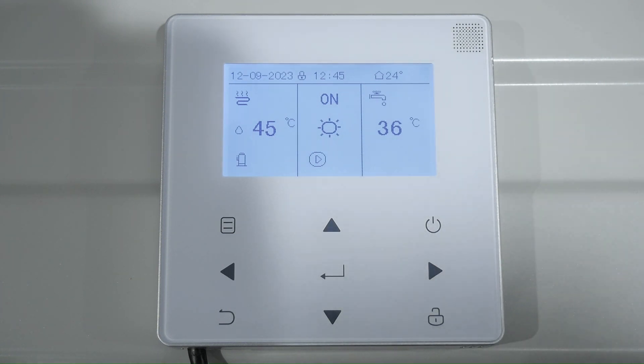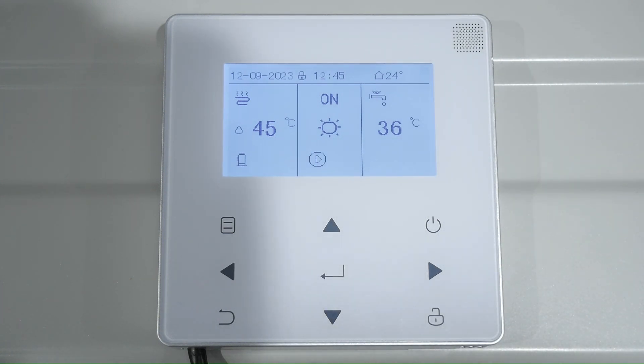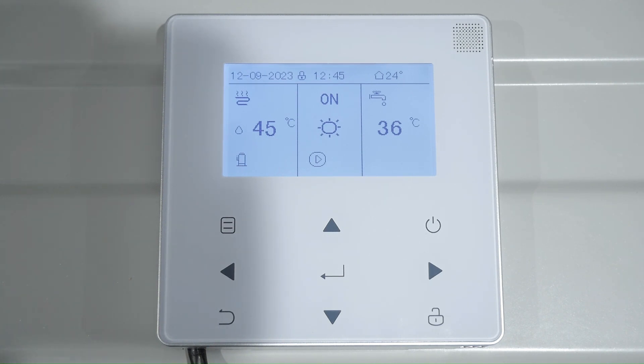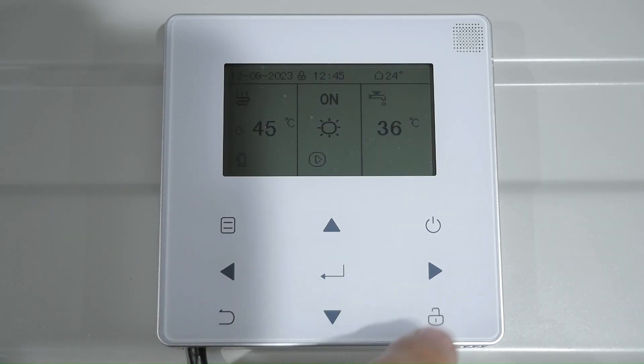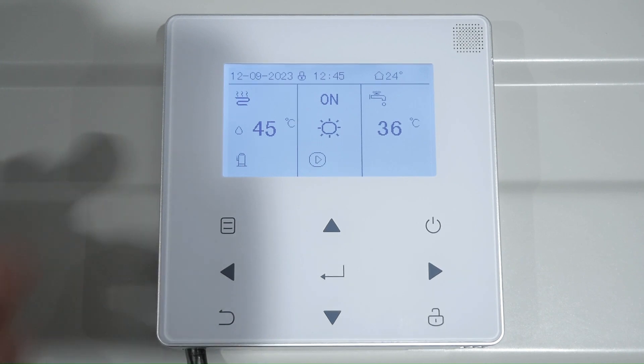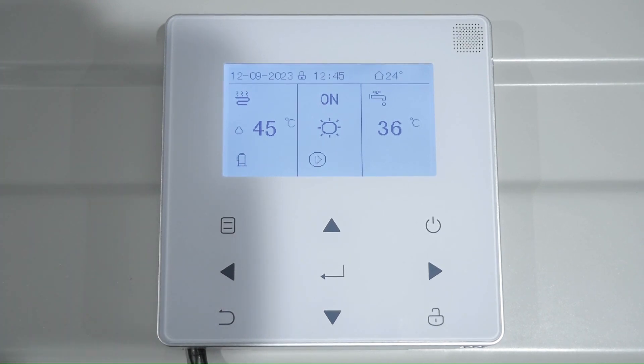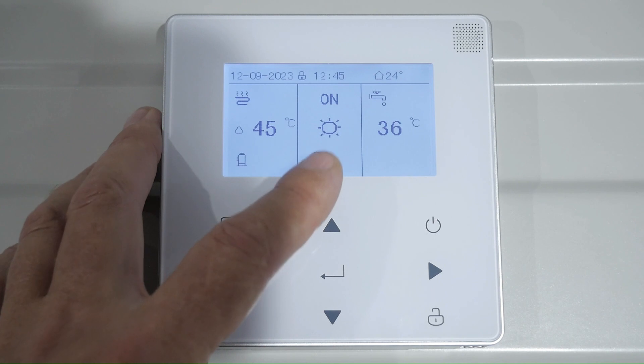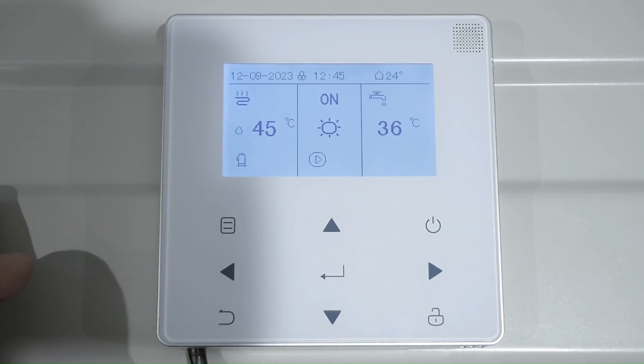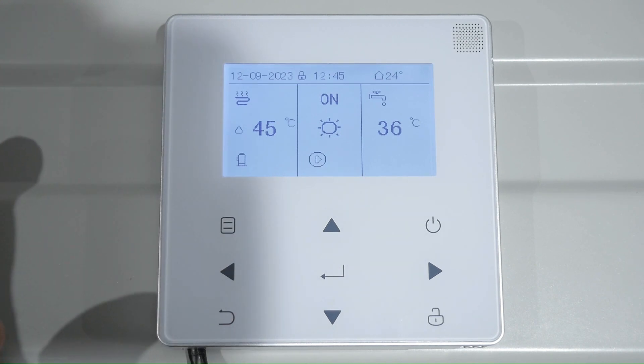The system is now up and running — you might be able to hear the fan running in the background. Noise is a little bit higher in here because we're internally in the training room. You can see the compressor symbol has come up and the pump symbol is up, so the unit is fully running. You wouldn't really need to look outside to check if the fan is running; you can see here that both the pump inside the unit and the compressor are running and it's live in heating mode.